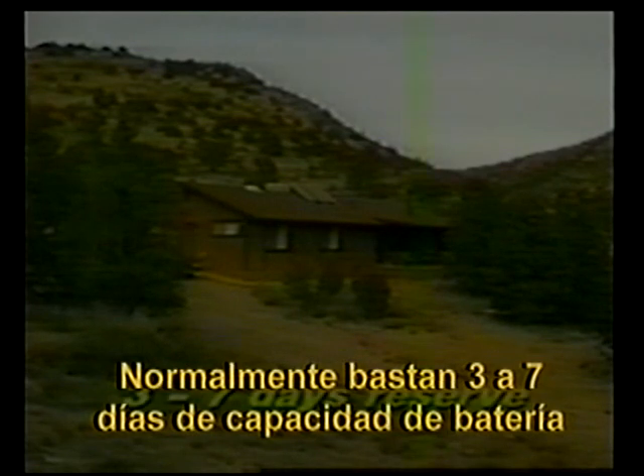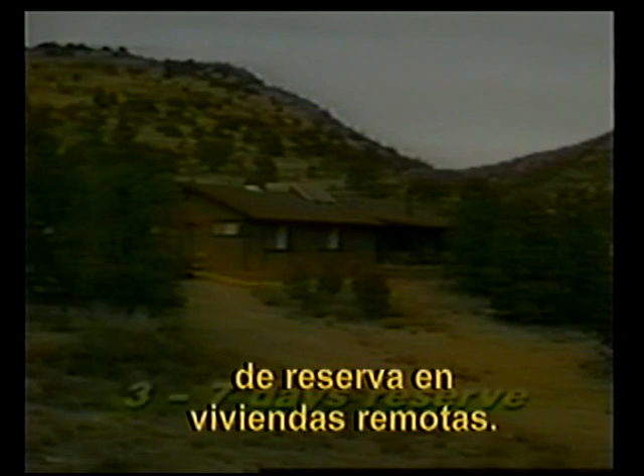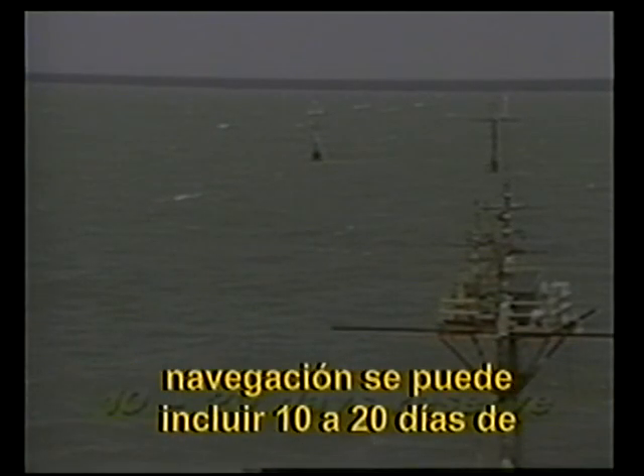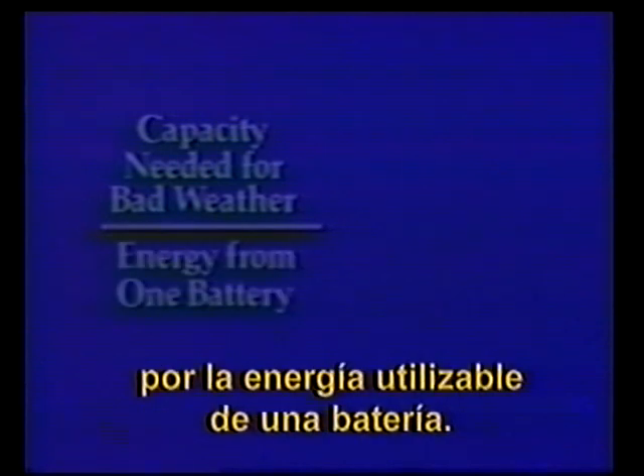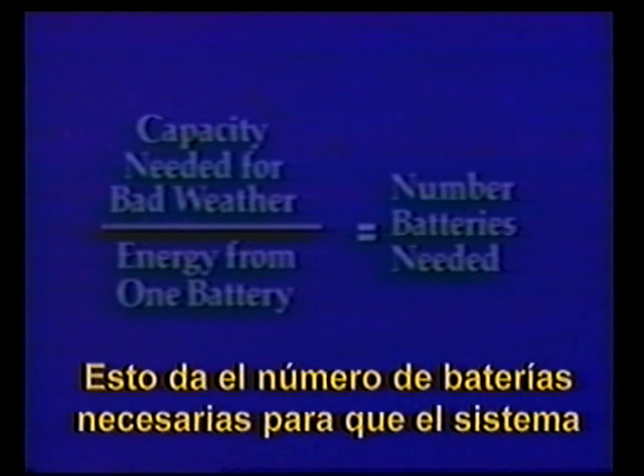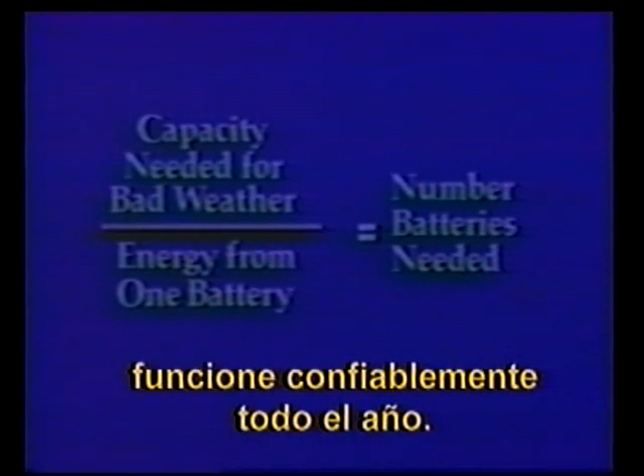Normally, 3 to 7 days of reserve battery capacity is plenty for remote homes. For remote transmitters or navigational aids, 10 to 20 days may be designed into the system for extra reliability. The capacity needed to operate all of the loads during the longest expected stretch of continuous stormy days is divided by the energy usable from one battery. This gives the number of batteries needed for the system to operate reliably throughout the year.